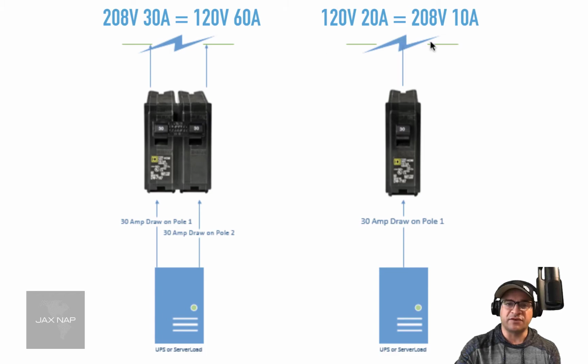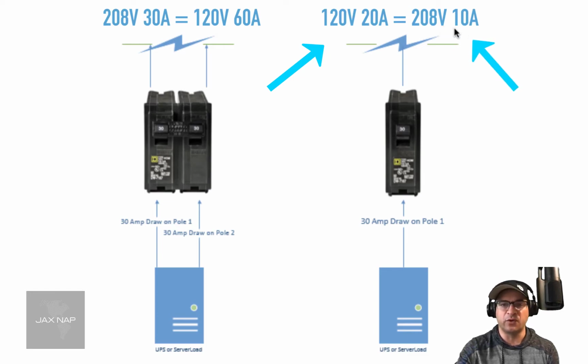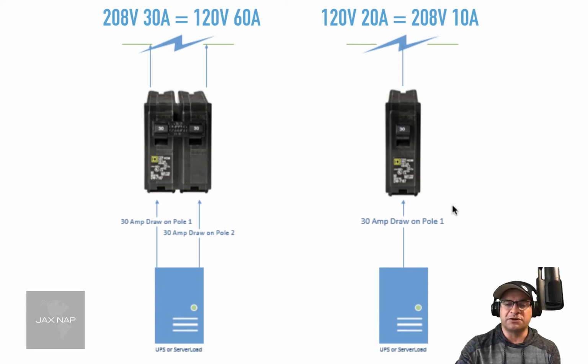So if I have a circuit here at 120 volts at 20 amps, it's the equivalent of 10 amps of 208 volts. So over here is more common of what people order, okay? So if we start to figure out what kind of equipment we're going to be needing in the data center and what we're colocating, if we select larger routers that require 208, or if we require SANs, I'm going to have to order a 208 circuit. But keep in mind that it's going to cost you twice as much in power.